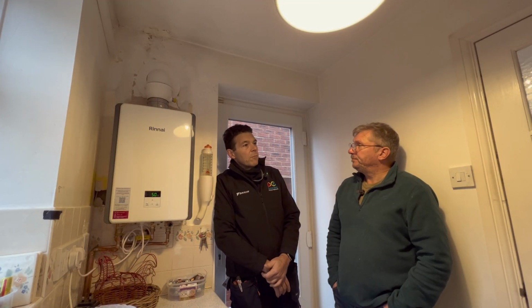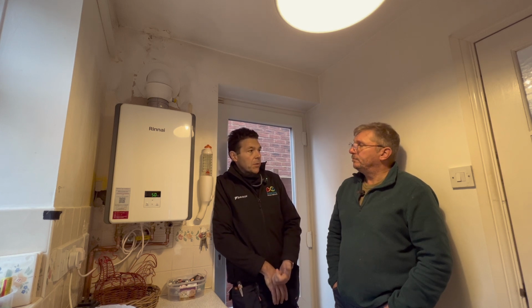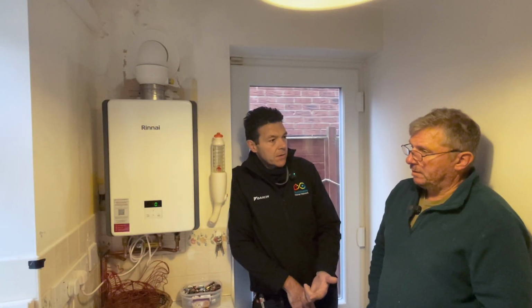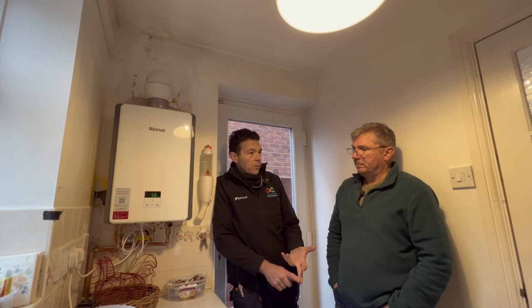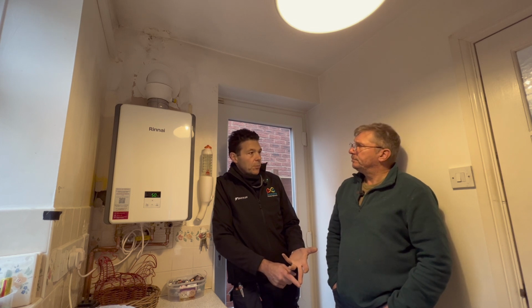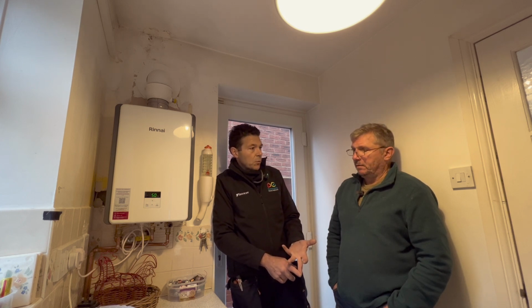So a recap on the decision you chose to go air-to-air over air-to-water: wall space being an issue, and elderly radiators. And also from a technical perspective, something that I looked at and spoke with you about was the fact that you have microbore pipework throughout the house. It would have been a bigger job, for sure. And you've got chipboard tongue-and-groove floors upstairs, so it would have been a big job retrofitting larger bore pipework suitable for an air-to-water heat pump system.